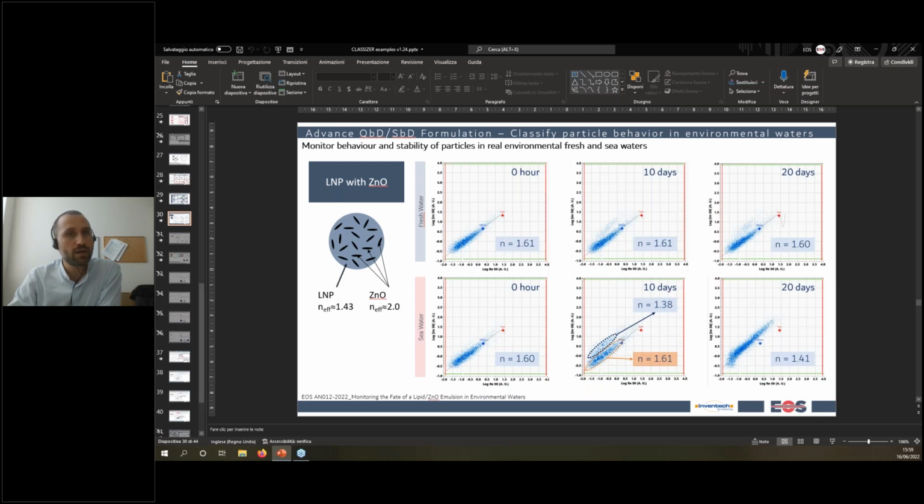It depends on the size of the particle. The system has 2 different optical lines for the analysis of particles larger than 1 micron and for particles smaller than 1 micron. We can say that the size of the beam is a few microns for smaller particles and a few tens of microns for larger ones.